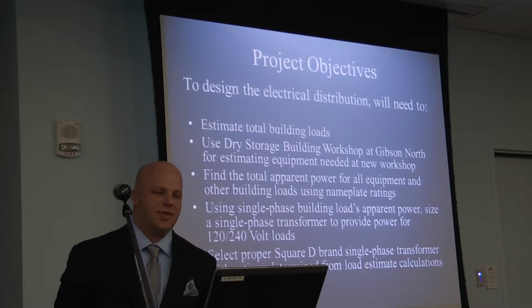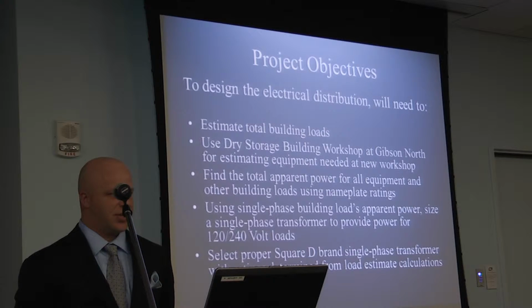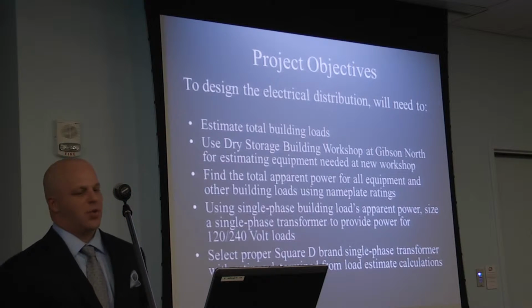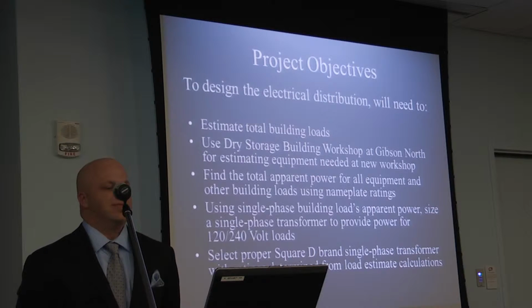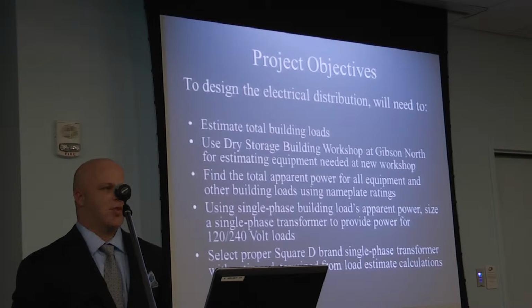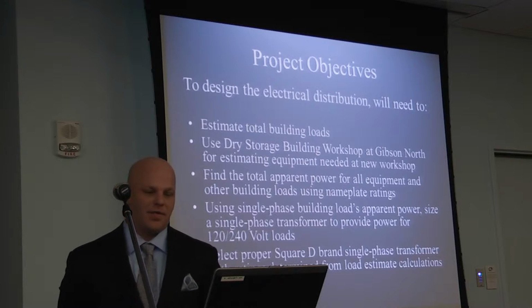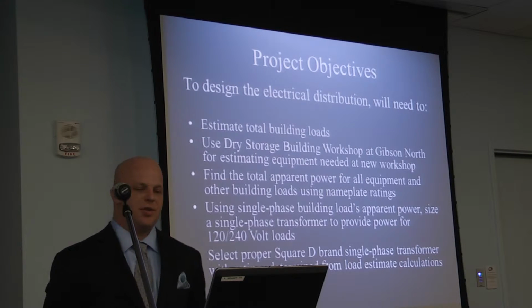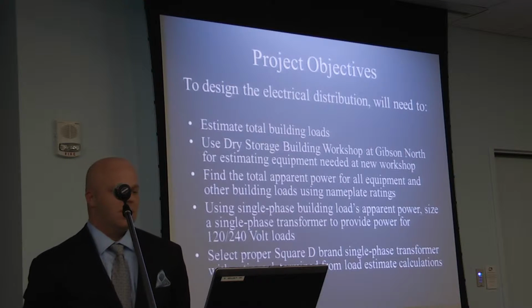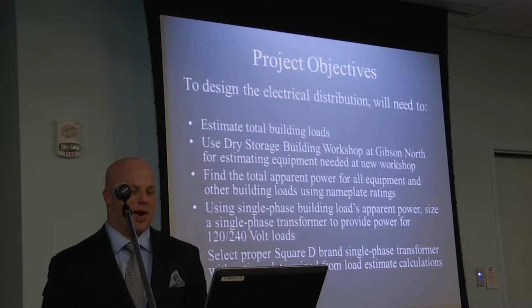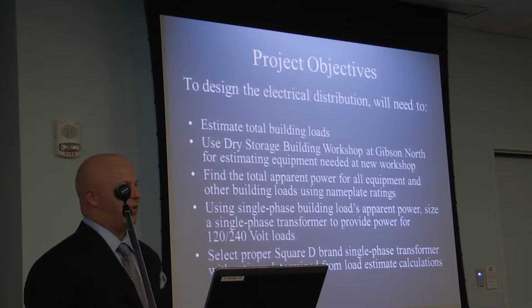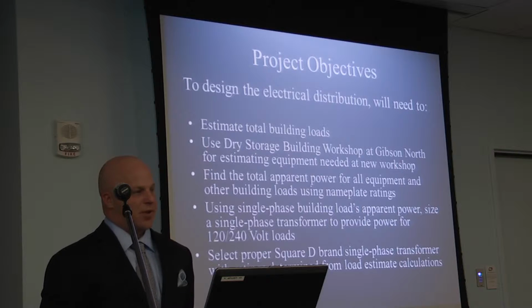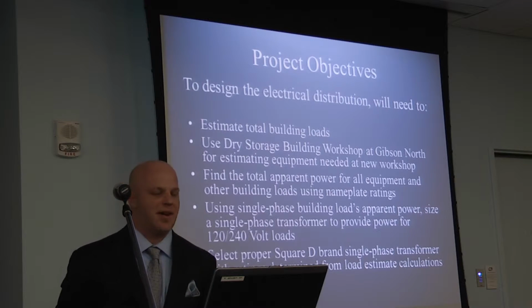The objectives of this project are to design the electrical distribution. I need to estimate the total building electrical loads, using the dry storage building workshop at Gibson North to estimate what type of equipment will be housed in the new workshop. Find the total apparent power for all the equipment and other building loads using the nameplate ratings. Using the single-phase building loads and apparent power, size a single-phase transformer to provide power for all the 120/240 volt loads, and select the proper Square D transformer based on the load estimate calculations.